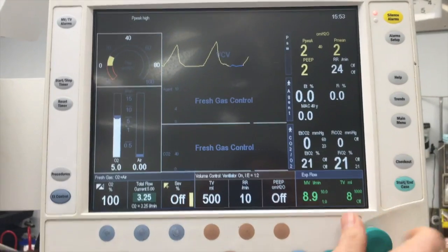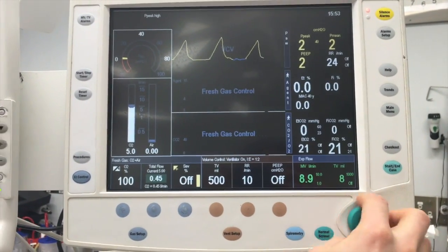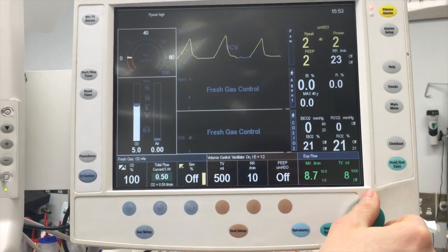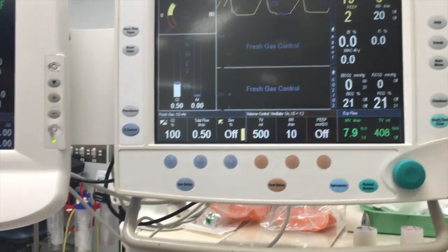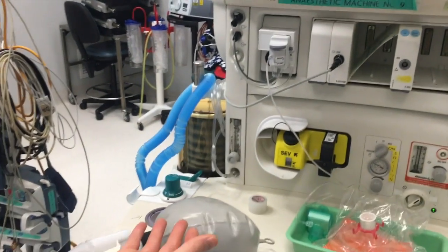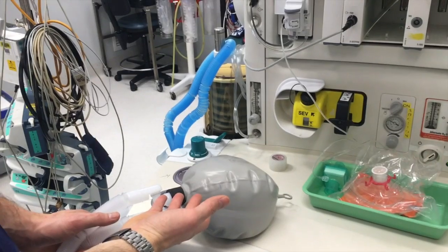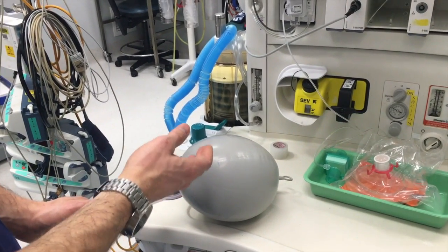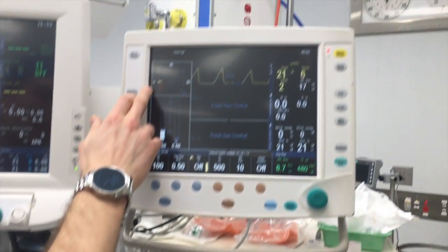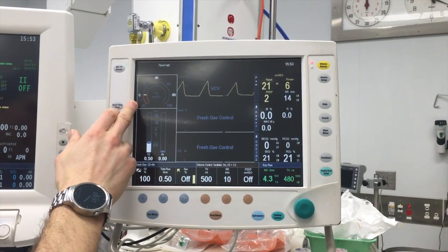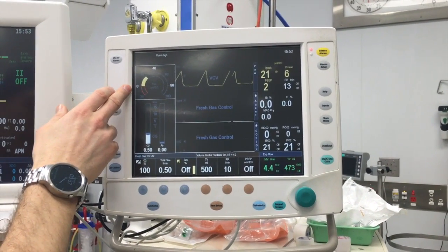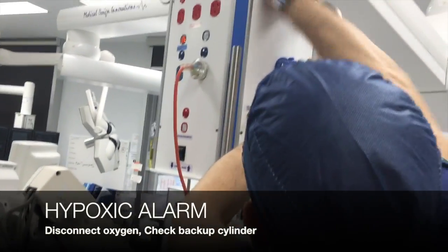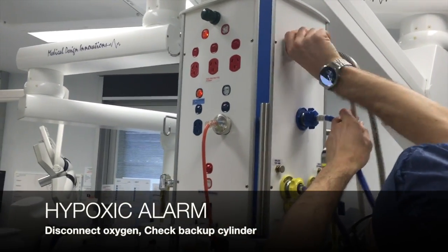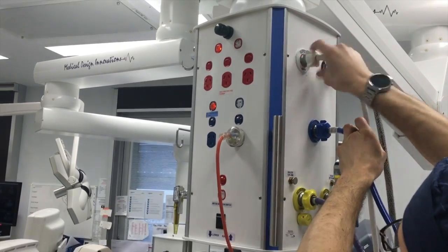To increase the ability to detect any leaks, drop the flow rate to only 0.5 litres a minute. Now check to see that adequate volumes are still achieved and that the bag doesn't slowly deflate. Check that adequate pressures are still being achieved and keep the ventilator running to give time for any small leaks to empty the bag. While ventilation continues, test the hypoxic alarm by disconnecting the oxygen supply from the wall.